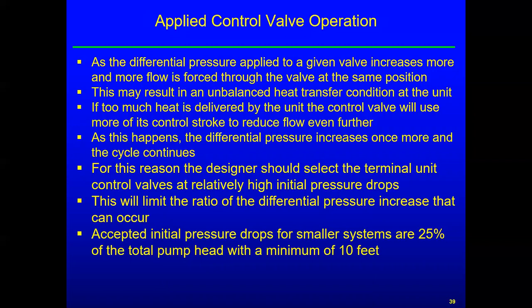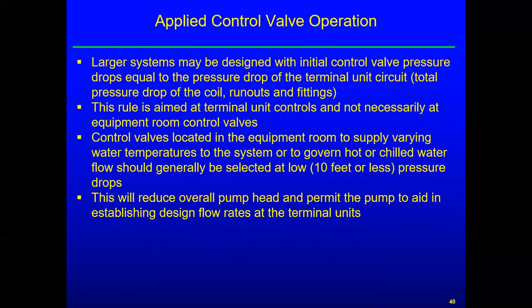Accepted initial pressure drops for smaller systems are 25% of the total pump head with a minimum of 10 feet. So that is a criteria for selecting control valves. And as we get toward the end of this presentation, we'll have a bunch of example systems where you'll actually be able to go out and select some particular control valves. But you need to remember that last bullet point. Larger systems may be designed with initial control valve pressure drops equal to the pressure drop from the terminal unit circuit. And that would be the total of the coil plus the runouts and fittings. So that would be from the distribution header, all the fittings through the coil and back to the return distribution pipe. So that's for larger systems.